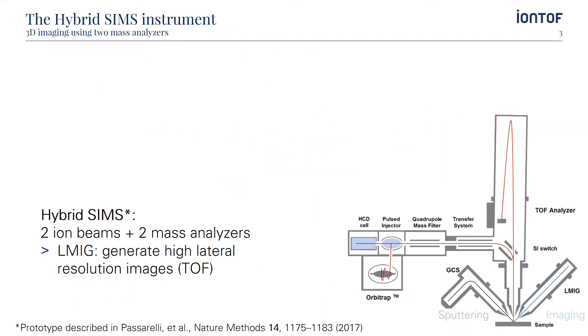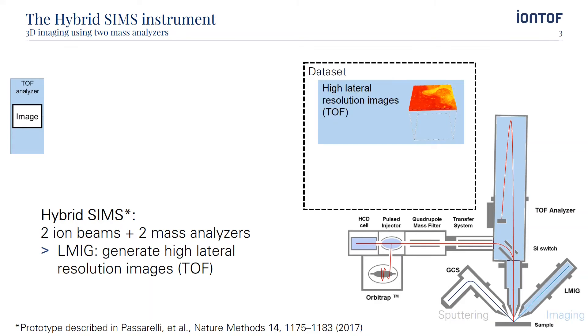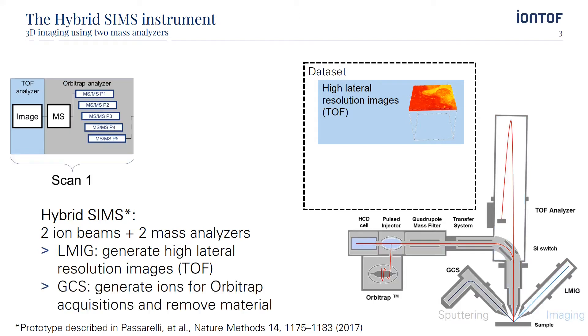The instrument used here is IONTOF's Hybrid SIMS, equipped with these two ion guns. However, the key feature is that it combines two mass analyzers: a time-of-flight and an Orbitrap mass spectrometer. The TOF is used to produce mass spectrometry images with high speed at high lateral resolution employing the liquid metal ion gun. In the subsequent material removal step, the Orbitrap serves as mass analyzer and acquires high-quality MS and MS-MS data from the exact same sample area, where the gas cluster ion source serves for material removal and ion generation.